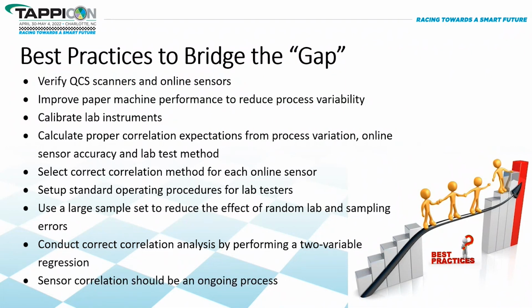The sensor correlation should be an ongoing process. It's not a one-time deal where you do it and you forget about it. Things change. The online sensor is being influenced by the environment, like the source decay for the basis weight, and the paper process furnish changes. So you always need the offline lab to correct the online sensor measurements, because sensor correlation gives us a system of checks and balances. It validates the slope and offset in the product code. So it needs to be an ongoing process. So these are the main best practices to bridge the gap to get good quality sensor correlation.